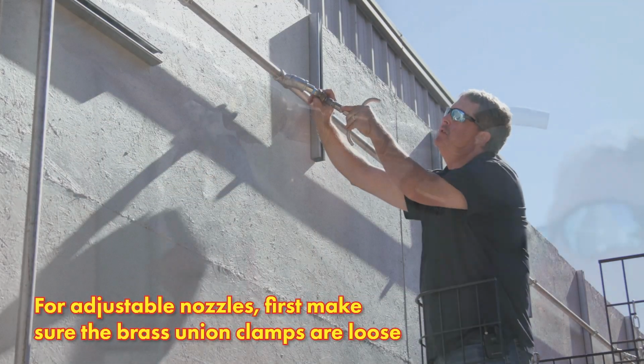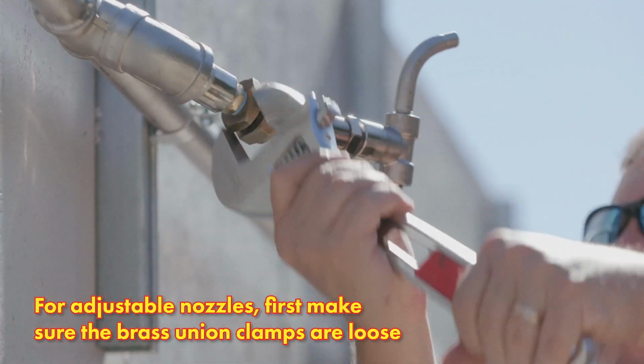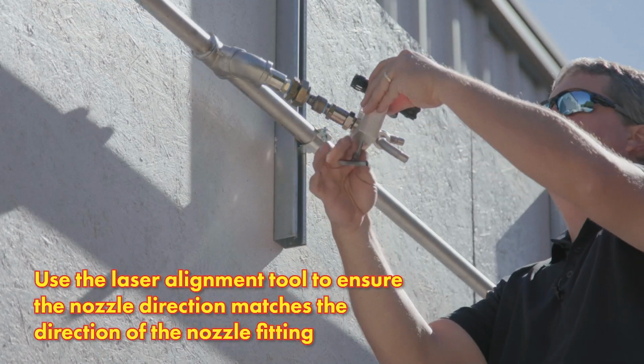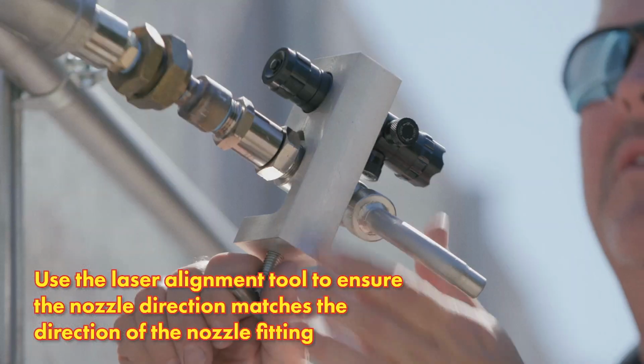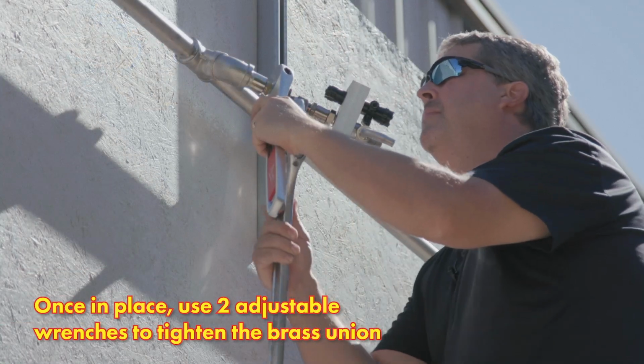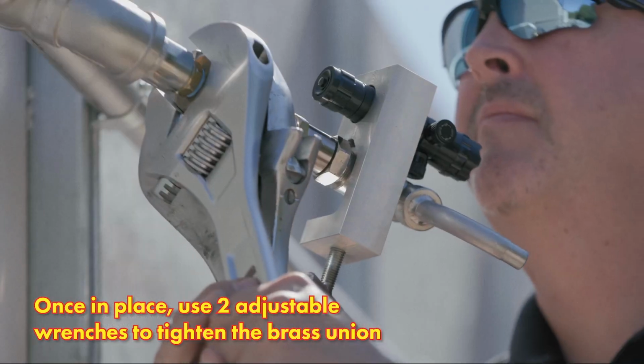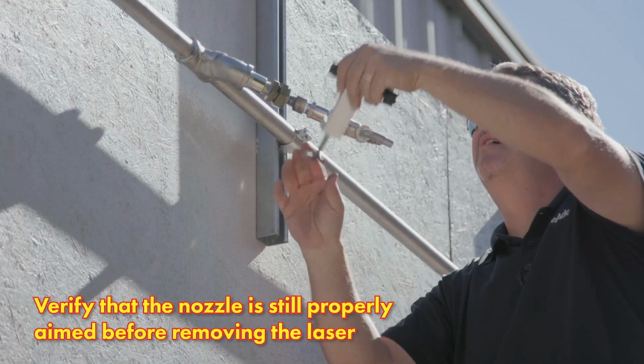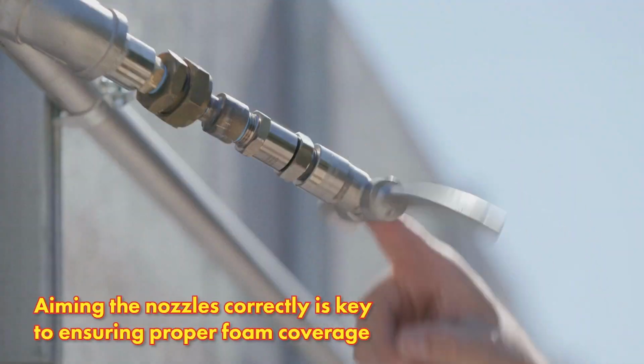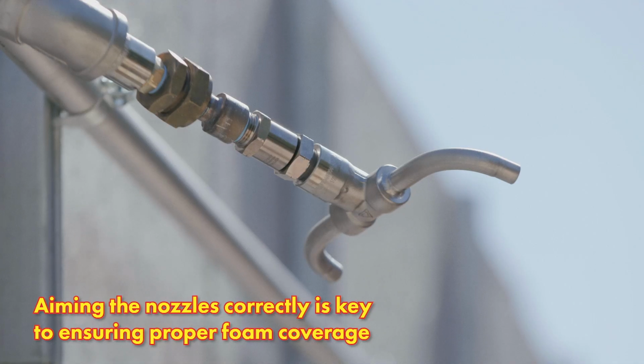For the adjustable nozzles, make sure the brass union clamps are loose and use the laser alignment tool to ensure the nozzle direction matches the direction of the nozzle fitting. Once in place, use 2 adjustable wrenches to tighten the brass union. Verify the laser is still properly aimed before removing. Aiming the nozzles correctly is key to ensuring proper foam coverage.